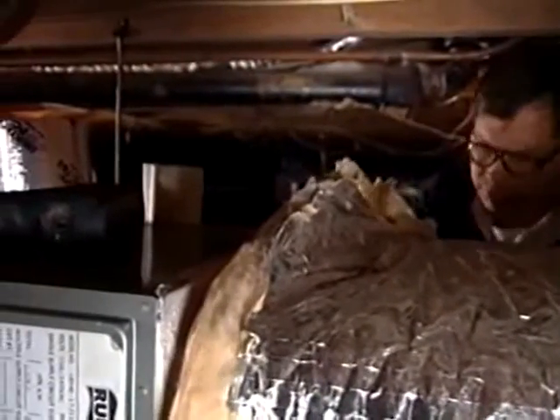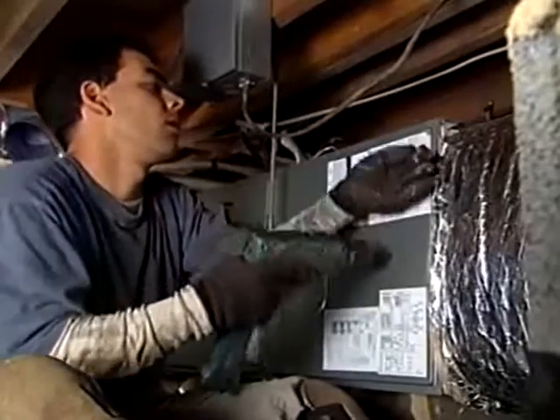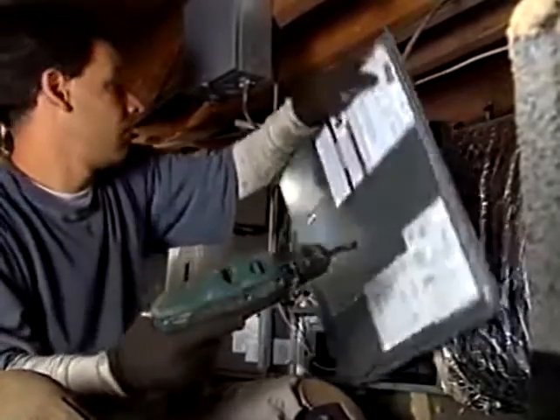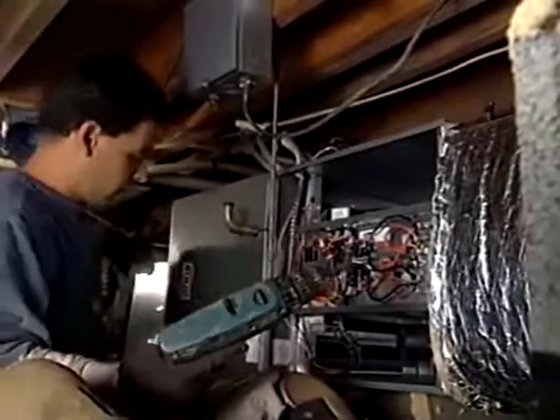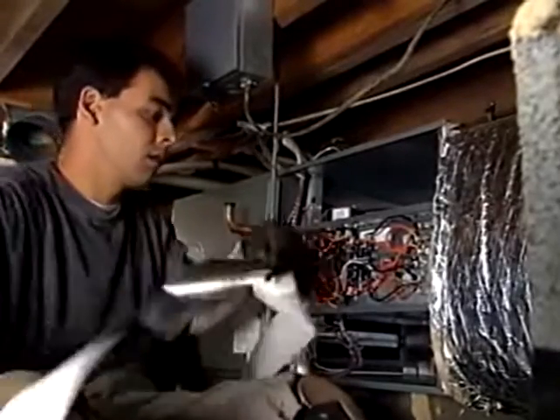After this connection is sealed, it's important to secure the insulation. This contractor holds the insulation in place with a UL 181 foil tape. Okay, about right there. Go ahead on up. Squish it in real good there. He takes the door of the air handler off, both to protect it and to make sure the seal isn't broken by opening this door in the future. As before, he uses fiberglass mesh tape around the entire connection and then seals it with mastic.